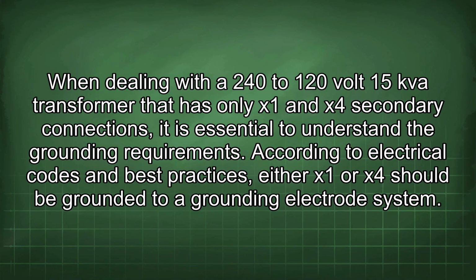When dealing with a 240 to 120 volt 15 kVA transformer that has only X1 and X4 secondary connections, it is essential to understand the grounding requirements. According to electrical codes and best practices, either X1 or X4 should be grounded to a grounding electrode system.